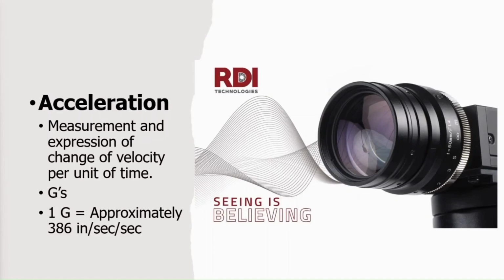And then a third way we could measure and express the vibration amplitude would be to use acceleration, which is the measurement and expression of change of velocity per unit of time. And the standard unit we use to measure and express acceleration is Gs, where 1 G would equal approximately 386 inches per second, or you might say inches per second squared.